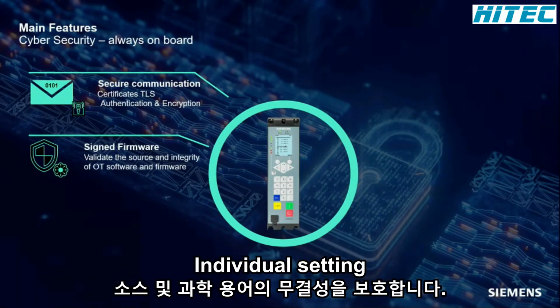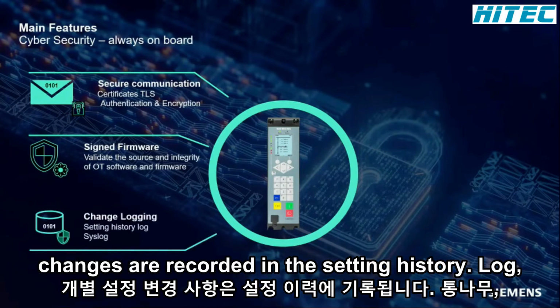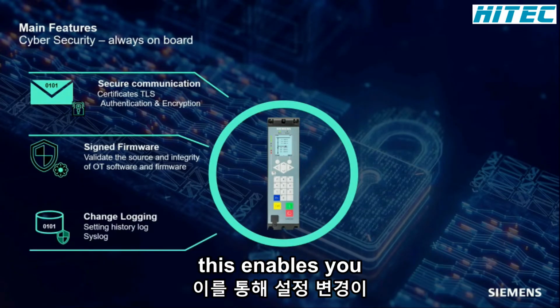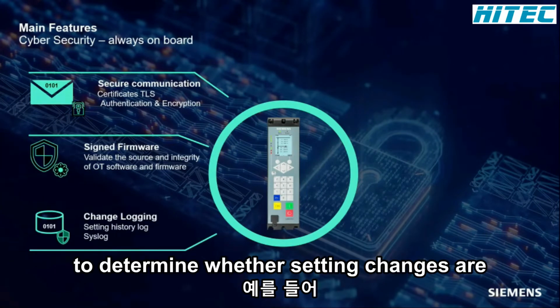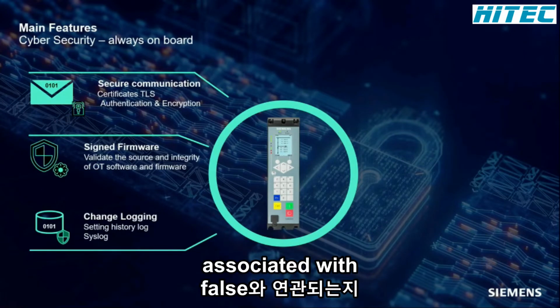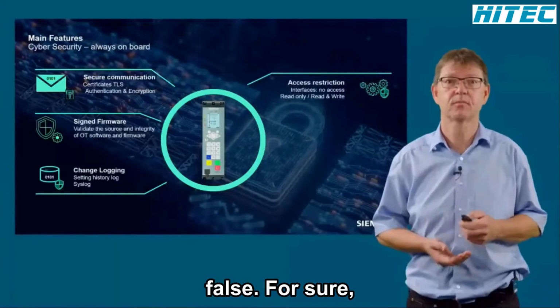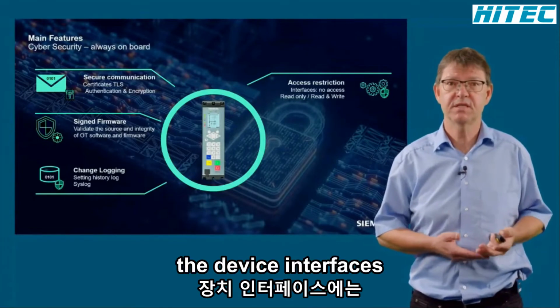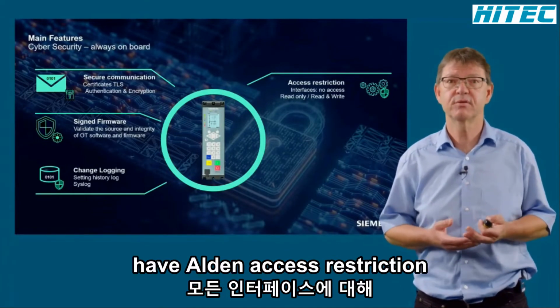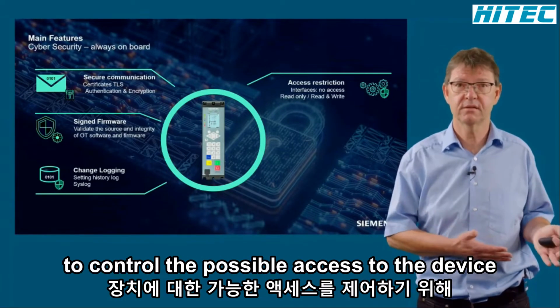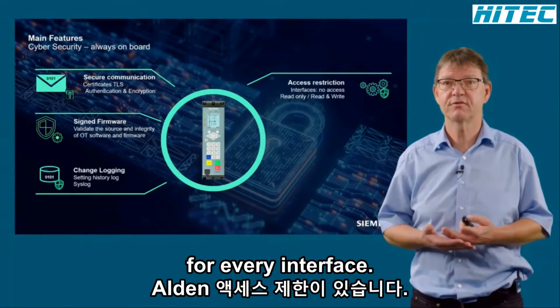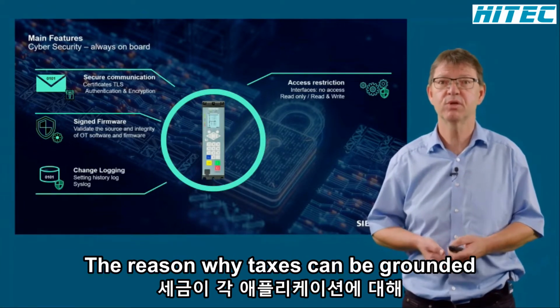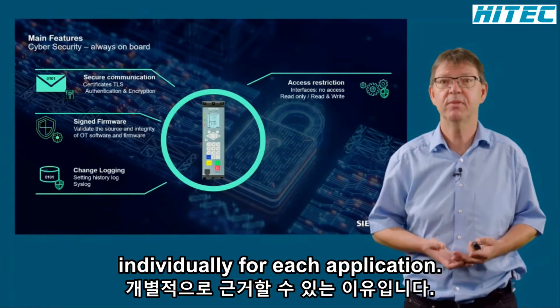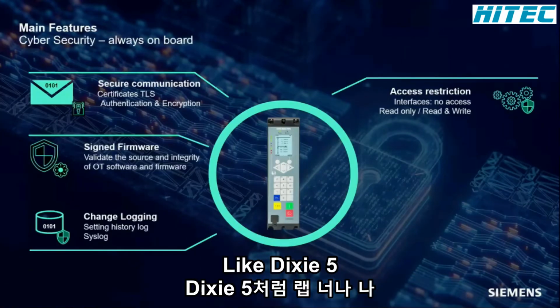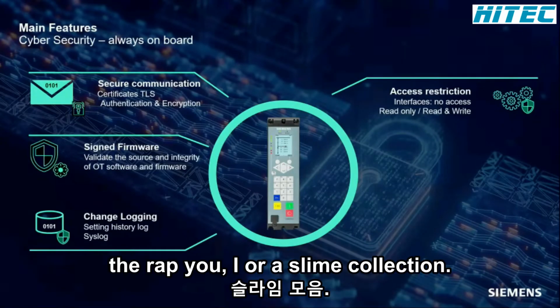All individual setting changes are recorded in the setting history log. This enables you to determine whether setting changes are associated with, for example, faults. For sure, the device interfaces also have an access restriction to control the possible access to the device. For every interface, the read and write access can be granted individually for each application, like DIGSI 5, the web UI, or a client connection.